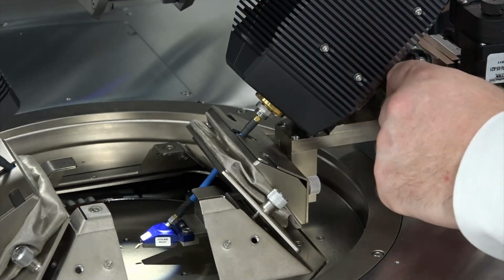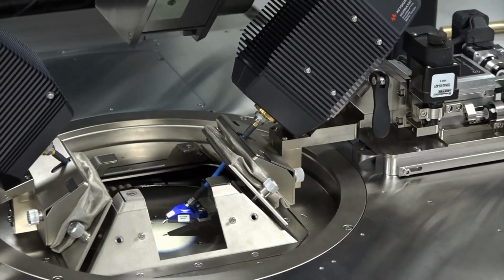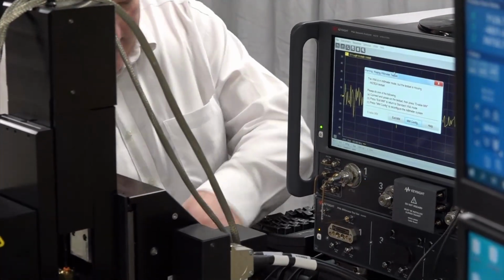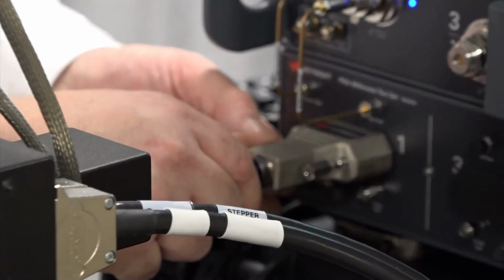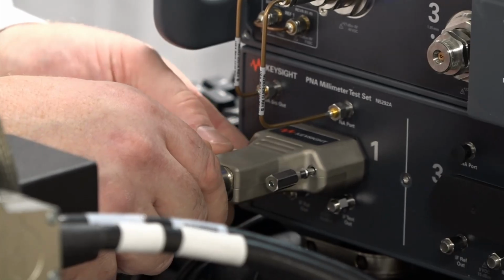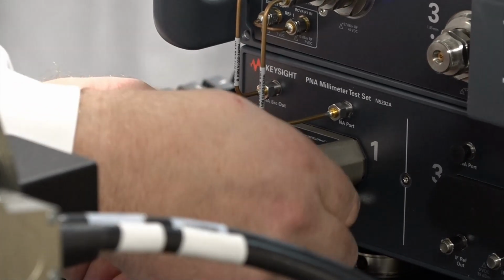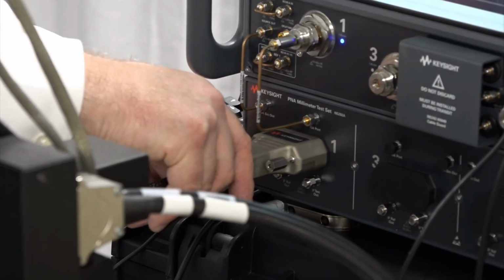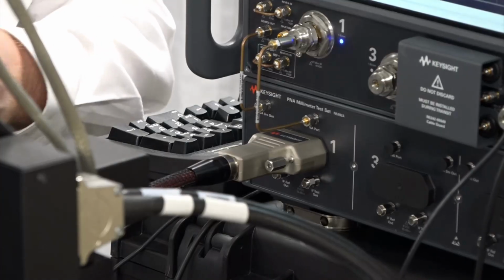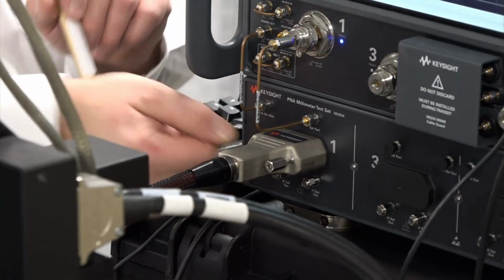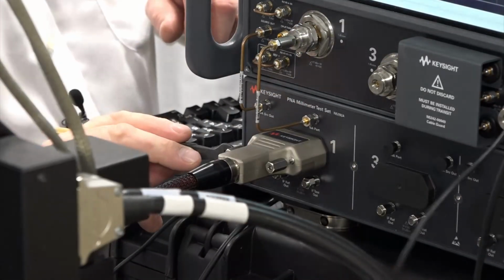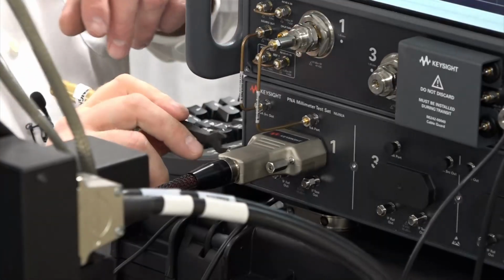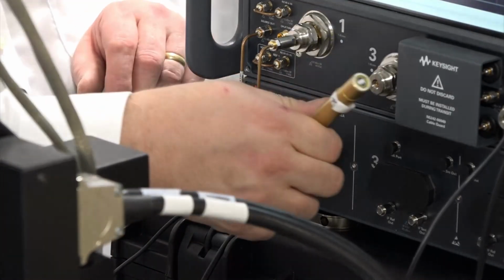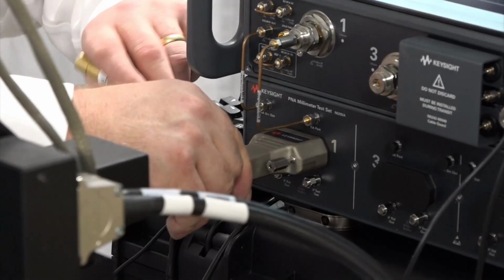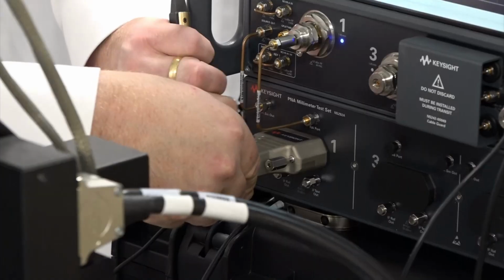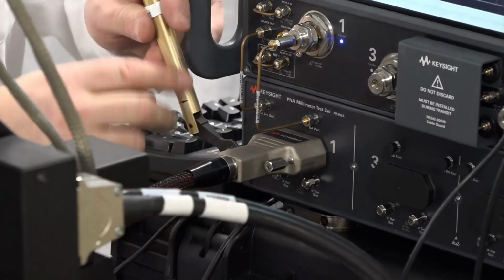Okay, so we now have, I'm just going to lock these off, and I'll put my connection back on up here. I'll push it nice and straight. Make sure it's turned off still. This should go pretty much all the way in by hand. And the last bit, we'll just use a regular torque wrench, making sure that we alternate torque it. We don't want it pulling all one way. Sometimes it helps to push it in by hand slightly. It's important that these are in properly, they can drift otherwise.